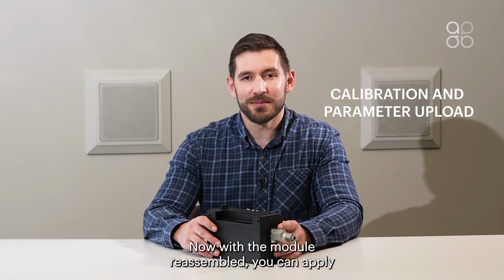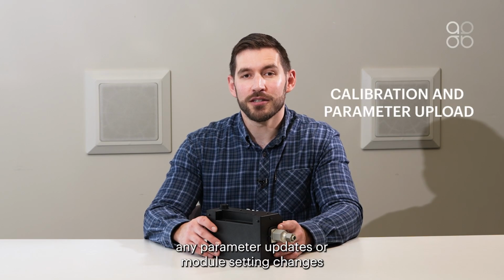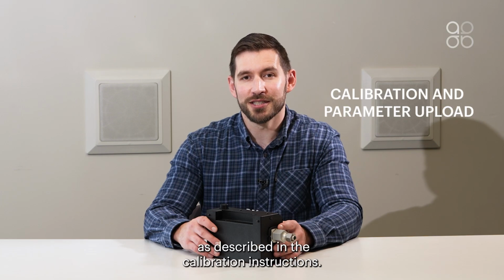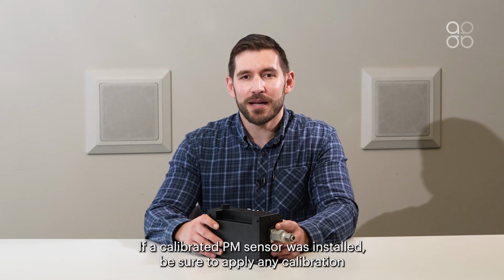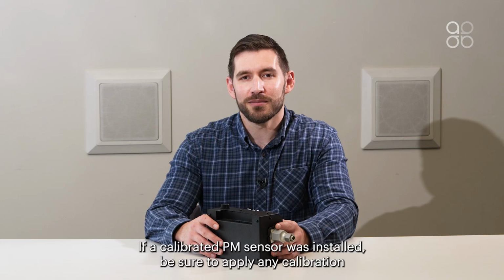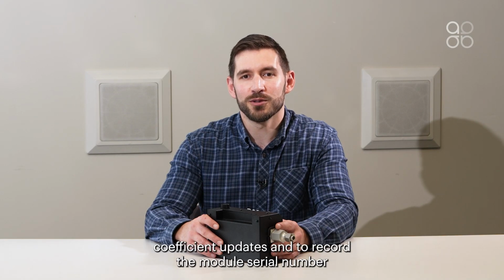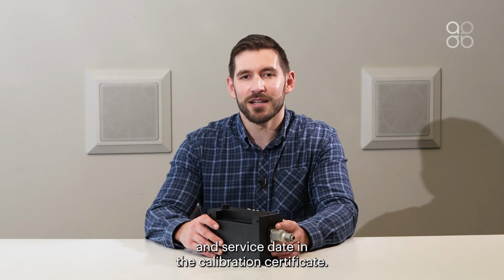Now with the module reassembled, you can apply any parameter updates or module setting changes as described in the calibration instructions. If a calibrated PM sensor was installed, be sure to apply any calibration coefficient updates and to record the module's serial number and service date in the calibration certificate.